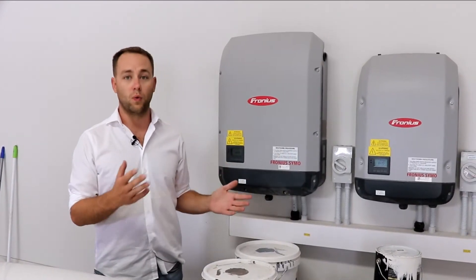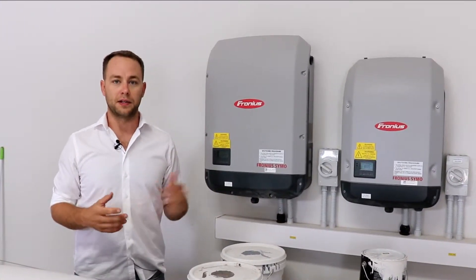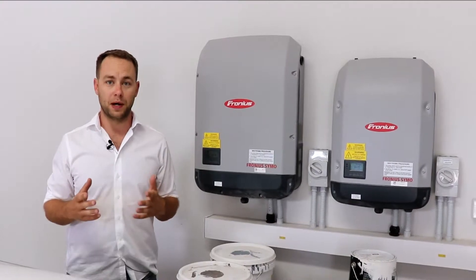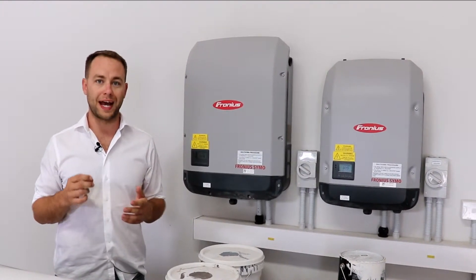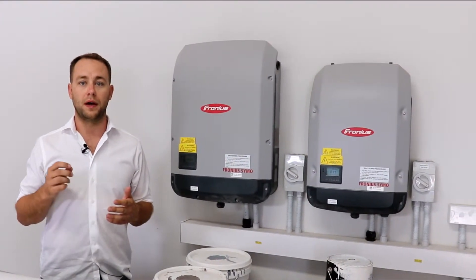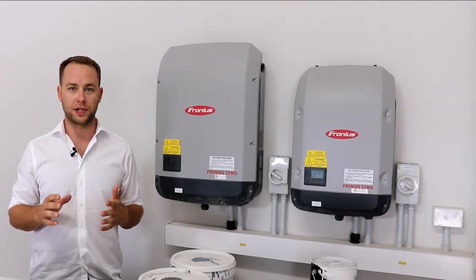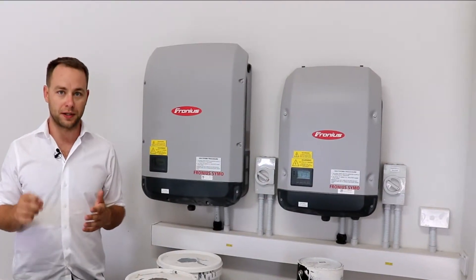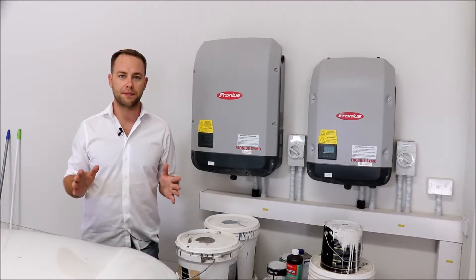When the sun's shining, solar power is being generated and converted from DC to AC. We have an AC heat pump here, and the heat pump converts every one kilowatt of electrical power into three kilowatts of heat. At this particular project we have a heat recovery heat pump, so we generate both three kilowatts of heat and three kilowatts of chill from that one kilowatt of power — amazing efficiency.